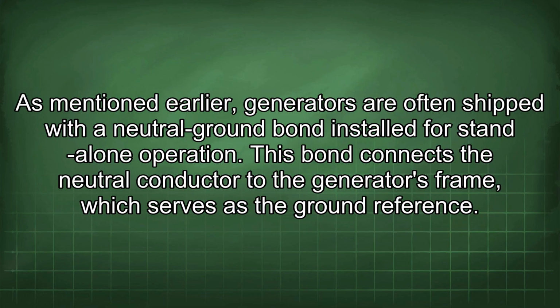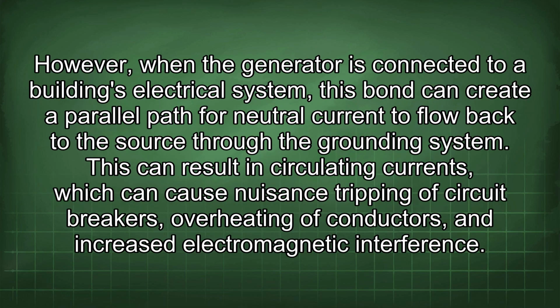As mentioned earlier, generators are often shipped with the neutral ground bond installed for standalone operation. This bond connects the neutral conductor to the generator's frame, which serves as the ground reference. However, when the generator is connected to a building's electrical system, this bond can create a parallel path for neutral current to flow back to the source through the grounding system.